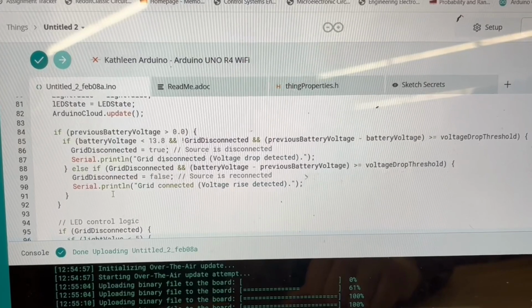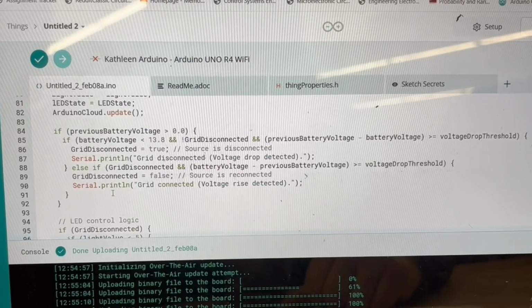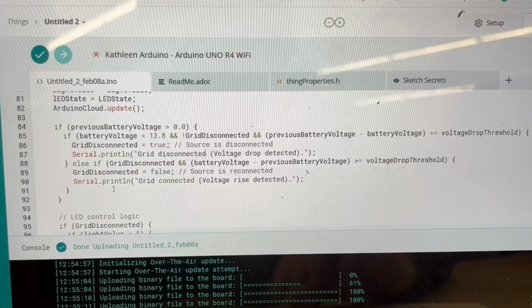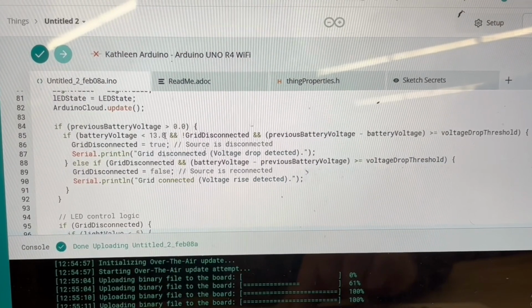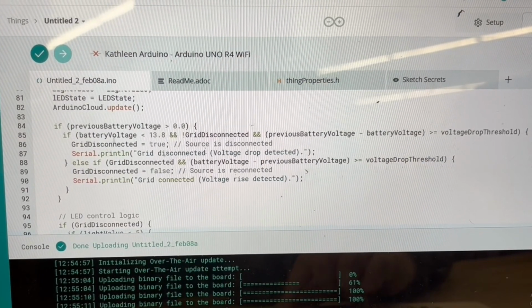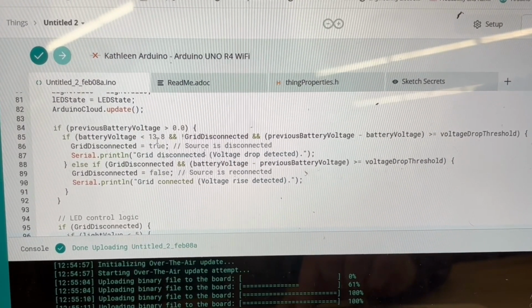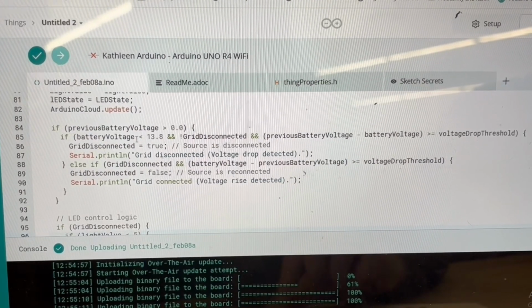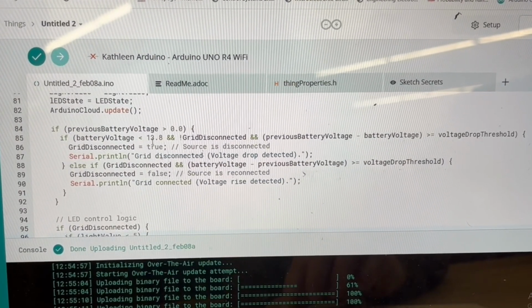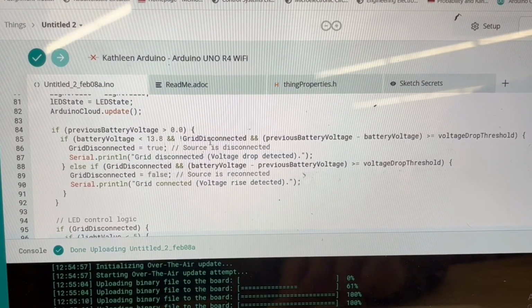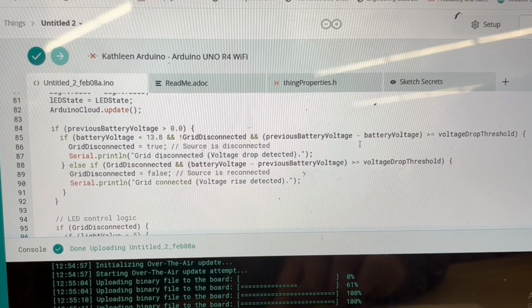Now we check for a voltage drop to indicate a grid disconnection. The threshold of less than 13.8 accounts for when the battery is fully charged and maintaining a charge. It will never reach 13.8 if it's not connected, but if it is at that point it'll fluctuate up and down, and we don't want to monitor that fluctuation as an actual grid disconnection.